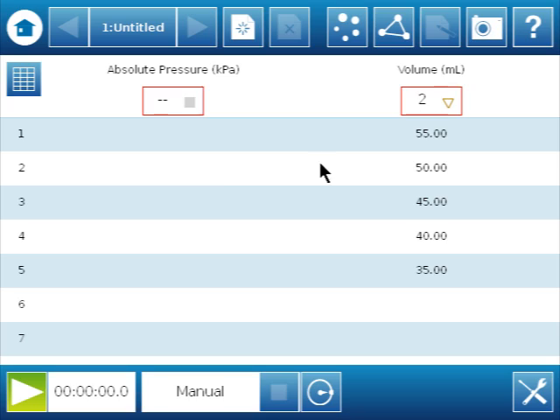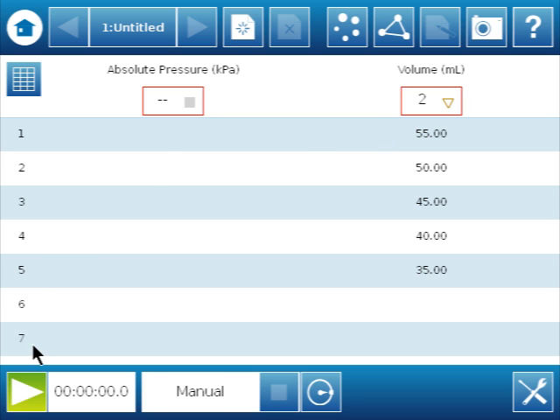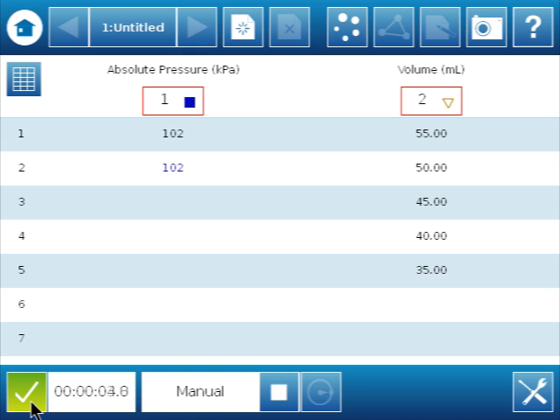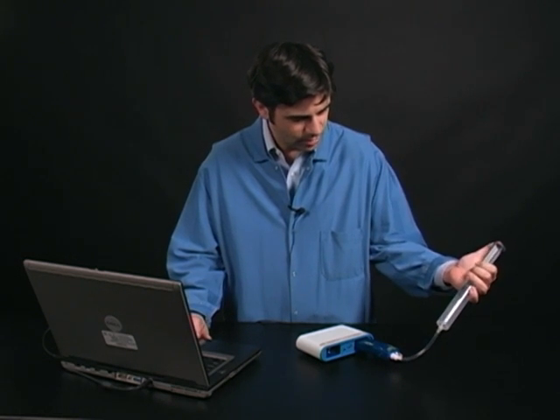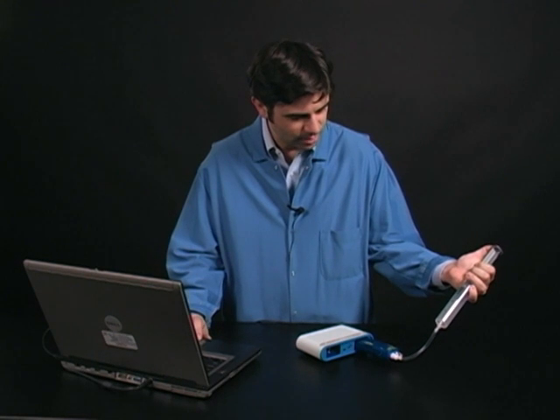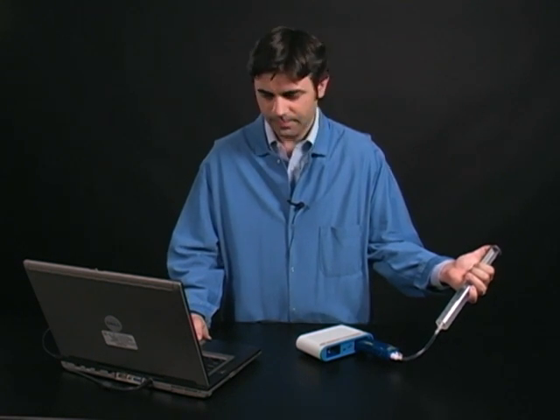On SparkVue I have preset the volumes, and I'm going to record pressures at those volumes manually. I'm going to hit go and I'm going to start recording, and I'm just going to move my syringe in 5 mL increments.